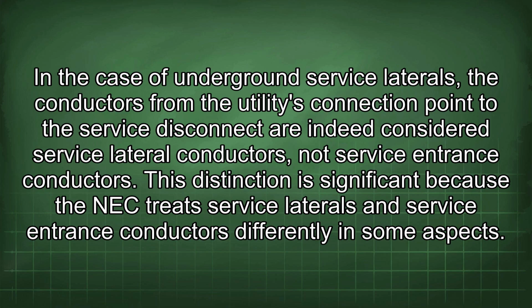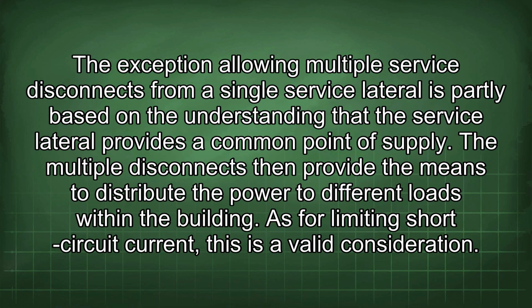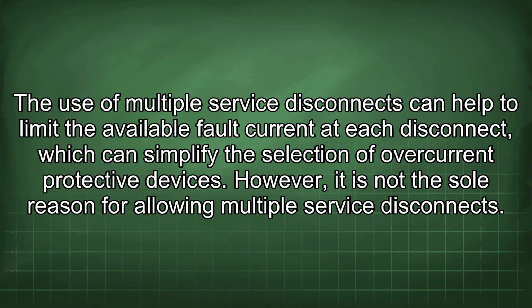This distinction is significant because the NEC treats service laterals and service entrance conductors differently in some aspects. The exception allowing multiple service disconnects from a single service lateral is partly based on the understanding that the service lateral provides a common point of supply. The multiple disconnects then provide the means to distribute the power to different loads within the building. As for limiting short-circuit current, this is a valid consideration. The use of multiple service disconnects can help to limit the available fault current at each disconnect, which can simplify the selection of overcurrent protective devices. However, it is not the sole reason for allowing multiple service disconnects.